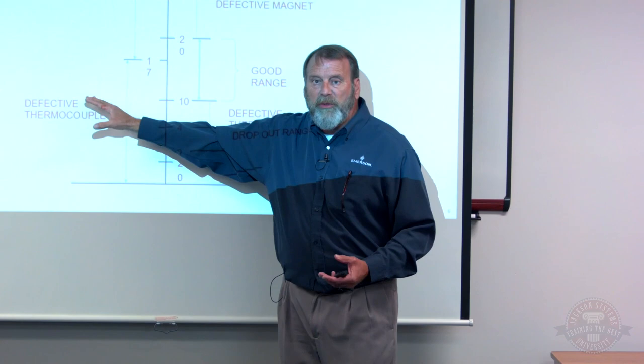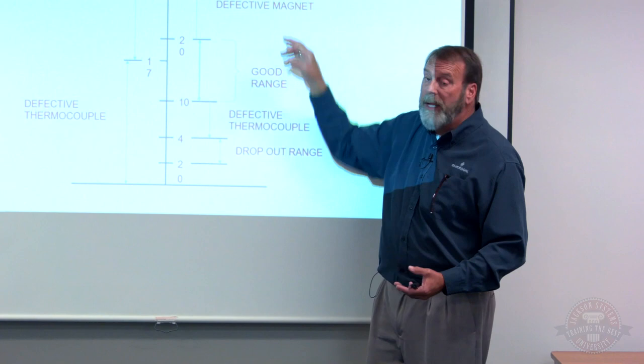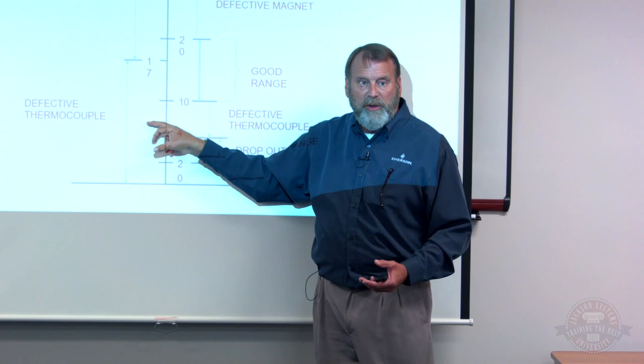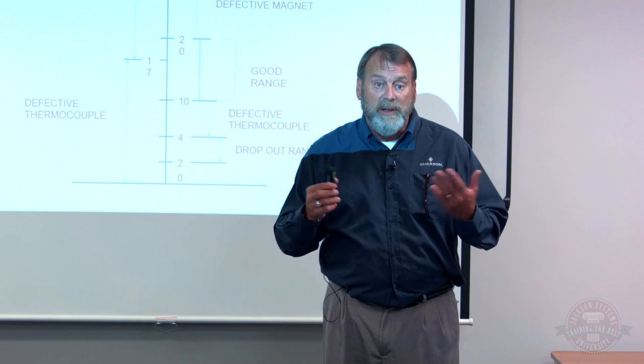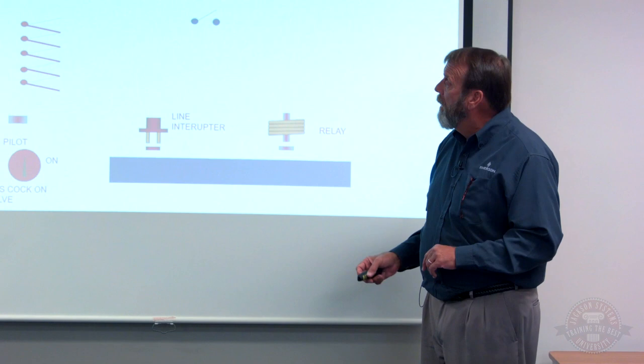So that's for the open circuit where it's actually hanging out in the air. If it's on the gas valve, that is closed circuit, and that's a little bit different under load. Instead of just having a go, no-go situation, we have a good range between 10 and 20 millivolts. So checking it under load, less than 10 or more than 20, you have a suspect defective thermocouple. So just a little fun fact for thermocouples. That's not why you guys are here.